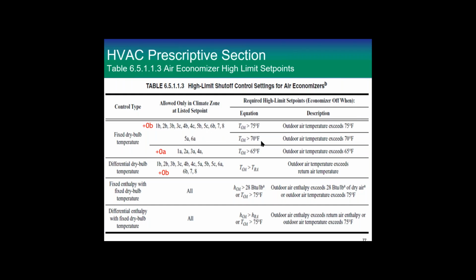All right. So then, if it's in 5A or 6A, which is in the middle of the country, we let you turn it off at 70 degrees. 1A through 4A, the hottest part of the deal, we let you turn it off at 65 degrees. These are dry, these are wet, so humidity has to do with that calculation. Differential dry bulb temperature: this is fixed, this is comparing the outside air to the return air temperature differential. Outside air greater than return air. When it gets to be greater than, you turn it off.